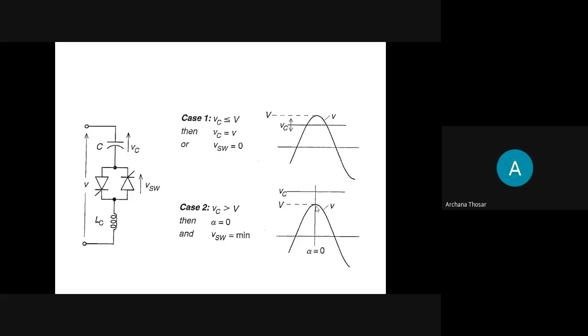This is the point where you switch on the device, introducing the capacitor into the circuit. When VC is higher than V, you can switch on the capacitor when VSW is minimum. So you switch on wherever it is minimum, at the peak of this AC voltage. This ensures transient-free switching, particularly for the thyristor switched capacitor.